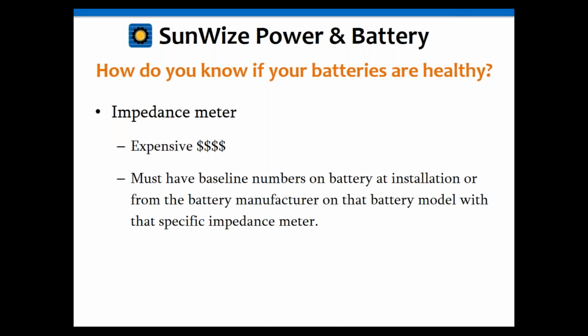And so unless you've got a baseline number from a brand new set of batteries you just installed, or you have that information from the battery manufacturer on that specific meter, because each meter measures that differently. They have a different number. It's measuring capacitance and inductance and all the things in the battery, resistance in it and things like that, and spits out a number, but different manufacturers do it in a different way. And it's different for different battery technologies. So you have to have that number for that specific battery model with that specific model of impedance meter. So if you don't have that and you don't have a baseline for measuring it, then it's worthless. It's not going to tell you anything.